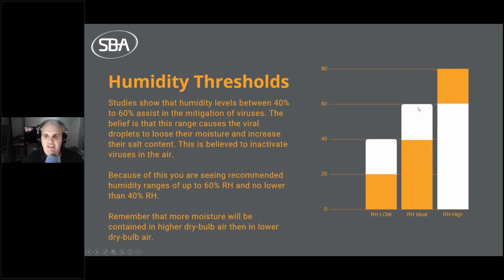So the humidity is relative to the temperature, and the moisture content is relative to the dry bulb temperature as well. So 80 degrees at 60% is much more grains per pound of dry air, of moisture, than 70 degrees at 60%. So understand that dry bulb, or temperature, has a factor in this calculation as to how much moisture energy is being introduced into the building and into the airstream.